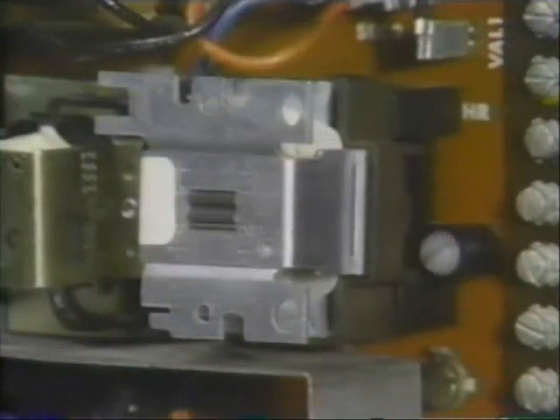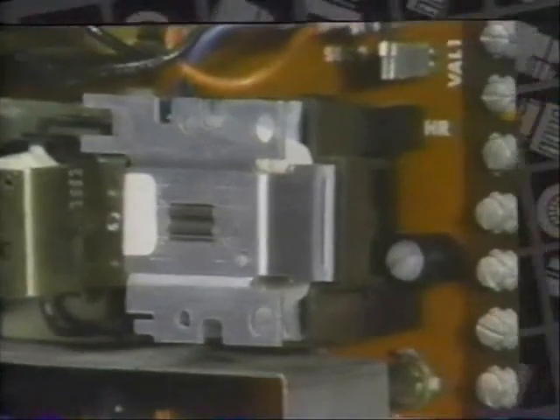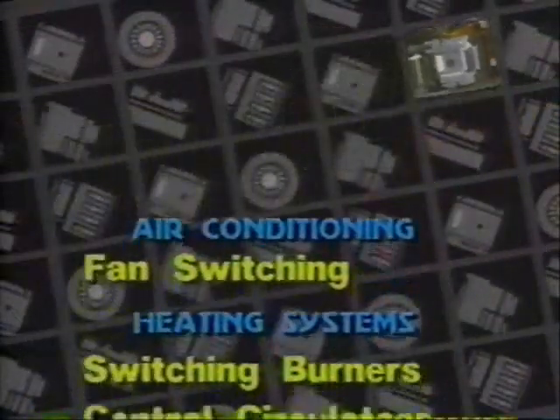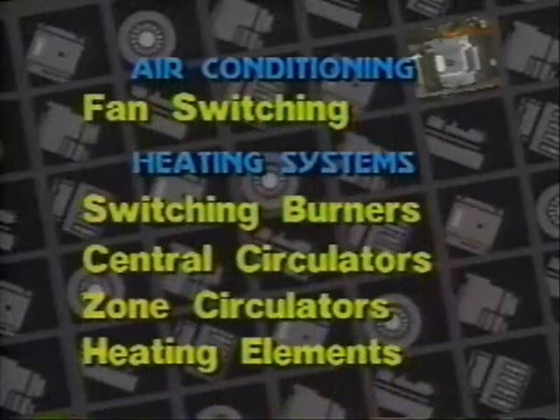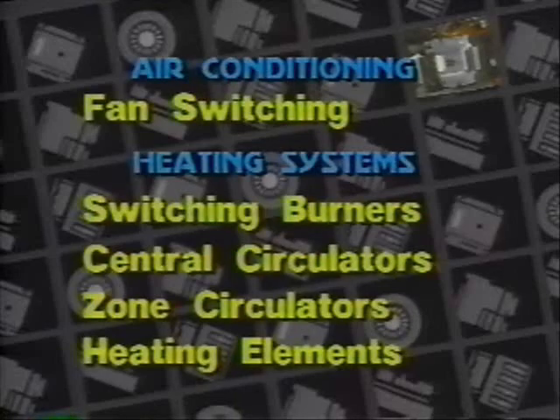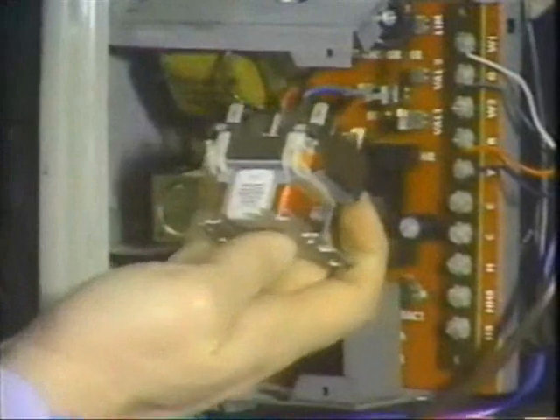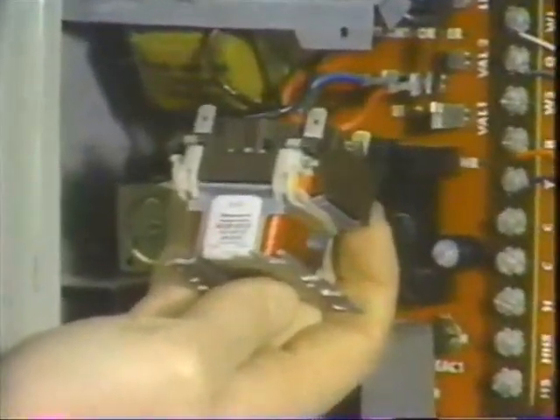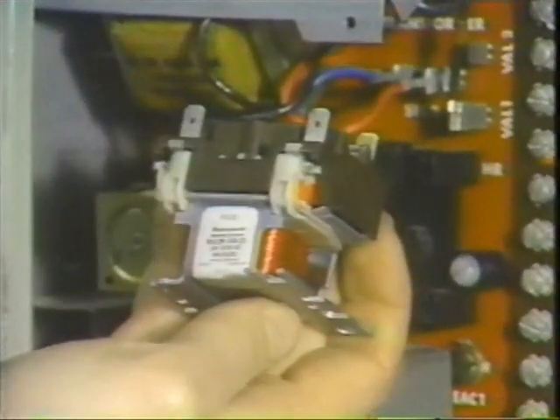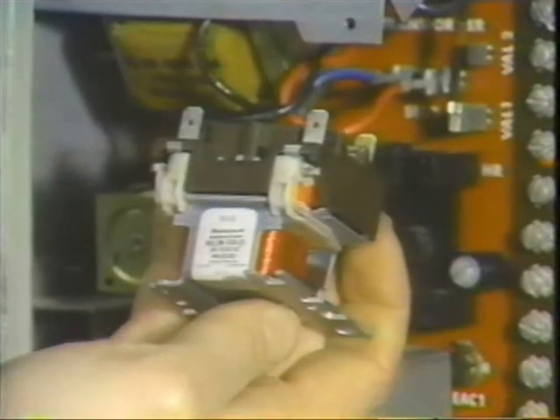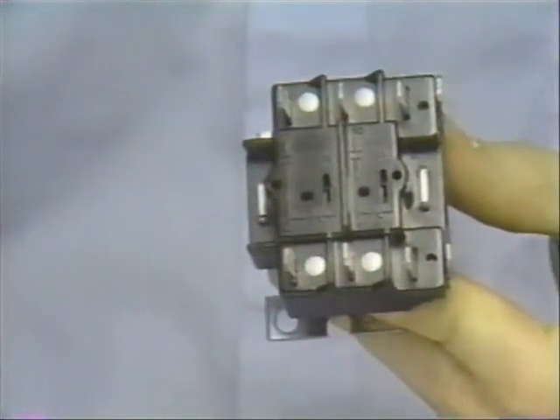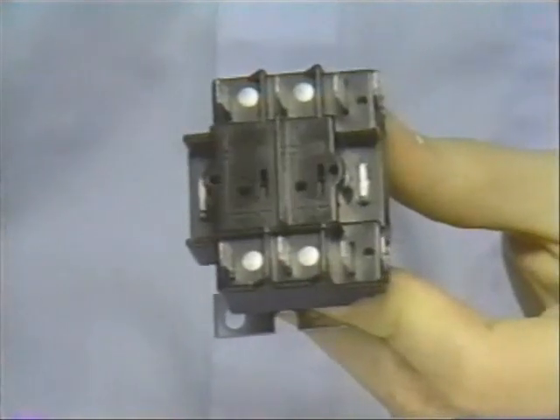In heating and air conditioning systems, very tiny relays are used in thermostats, and larger ones have a variety of other applications. Relays control fan switching in air conditioning systems and switching for burners, central circulators, zone circulators, and heat elements in heating systems. Relays are the mediators of electronic systems. They make it possible for different circuits with different voltage and load requirements to work together for effective control. While there are many types of relays, they're all built on the same principle.